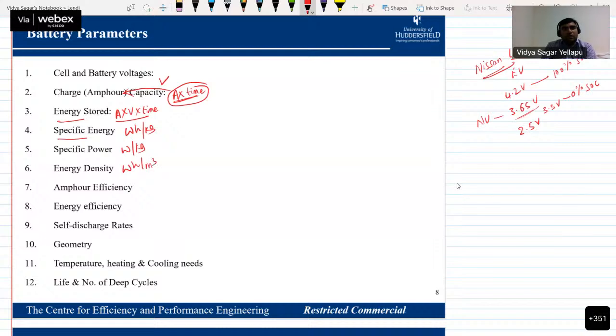Ampere hour efficiency. So what are the ampere hours given to the battery? That means the ratio of ampere hours obtained from the battery to the ampere hours given to the battery to make it fully charged, to the state before the discharge has been done. Energy efficiency: how much energy was taken out, and what is the energy given to the battery. So the ratio of energy output to the energy input is energy efficiency.